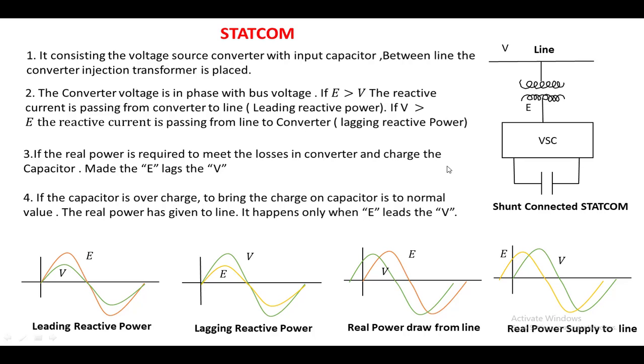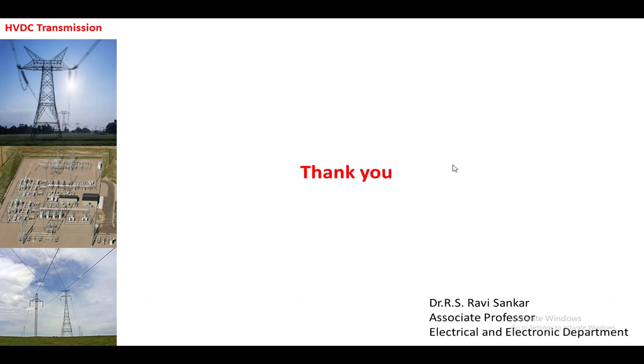If the capacitor is overcharged, discharging is accomplished when E leads V. By controlling both the magnitude of E relative to V and the angle between them, the STATCOM can control both real and reactive power. The STATCOM is used in HVDC transmission systems to supply or absorb reactive power, maintaining voltage at any given bus. Thank you very much for watching this video.